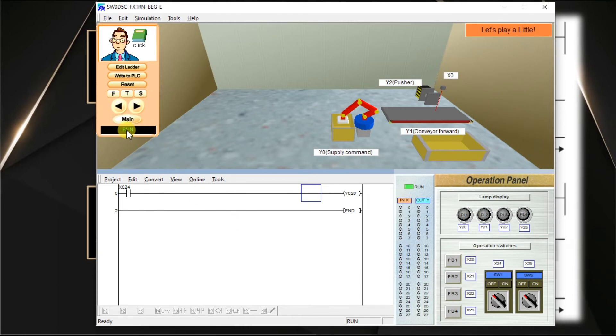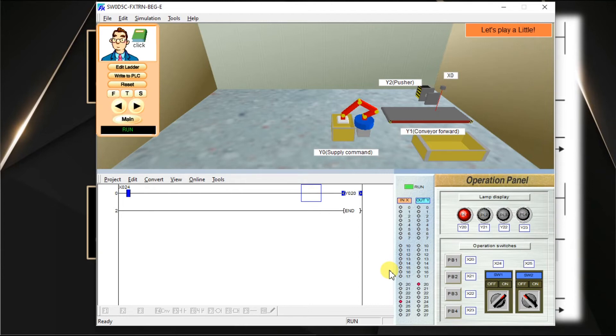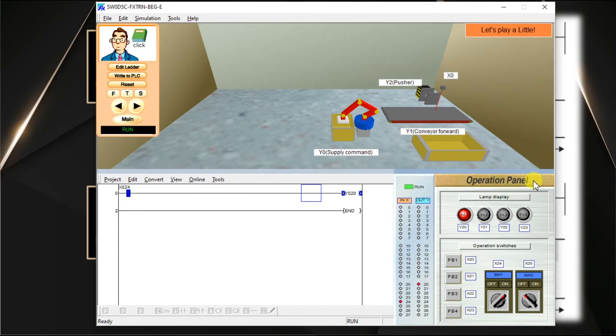The PLC mode is run mode again, so now we can do the simulation. Click on Switch 1 — input X24. The state is currently off; I am making it on. This is the selector switch — one click changes the state from off to on, and it stays that way until you click again. My input is on and output is also on. You can see the same status on the I/O table: X24 is on, shown in red. Output Y20 is also on. On the operation panel, output lamp 1 is on, shown in red. Making input off — output is also off.